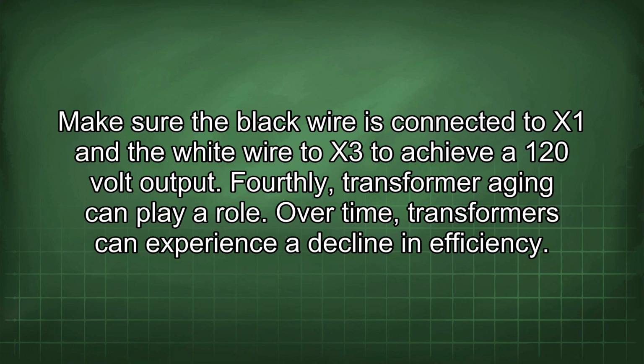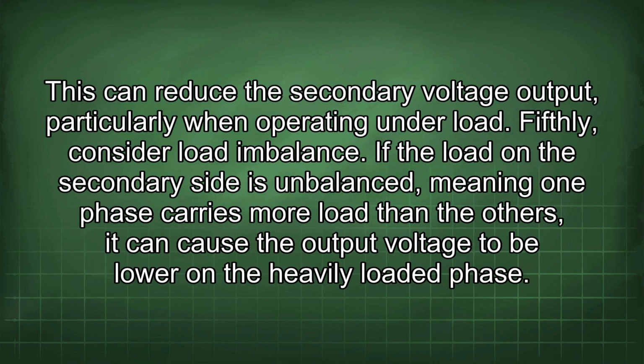Over time, transformers can experience a decline in efficiency. This can reduce the secondary voltage output, particularly when operating under load. Fifthly, consider load imbalance. If the load on the secondary side is imbalanced, meaning one phase carries more load than the others, it can cause the output voltage to be lower on the heavily loaded phase.